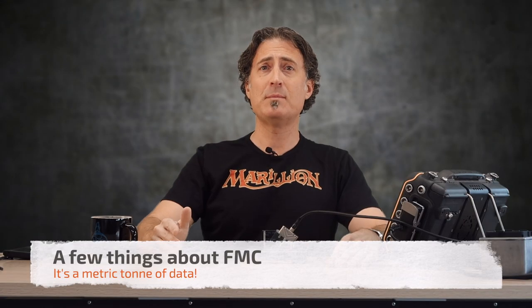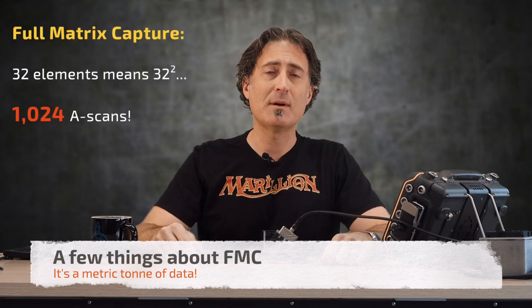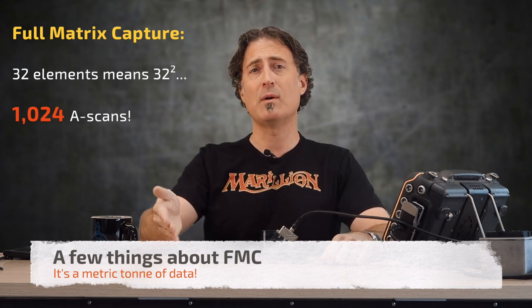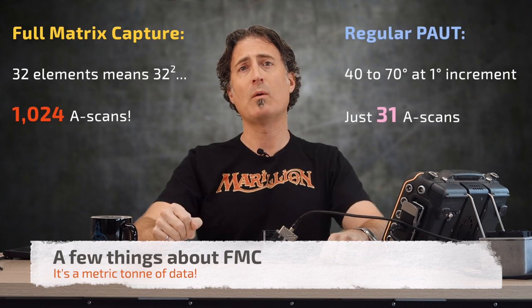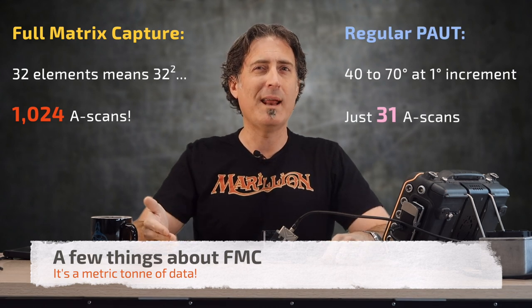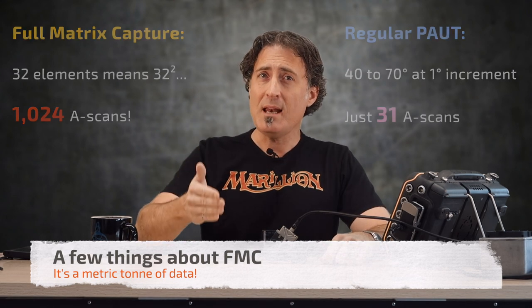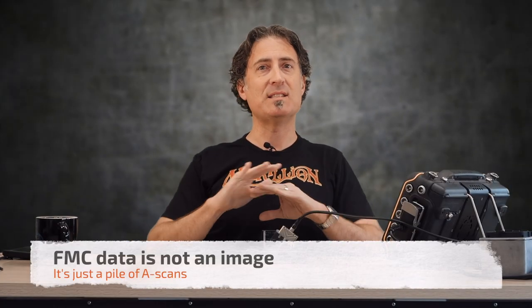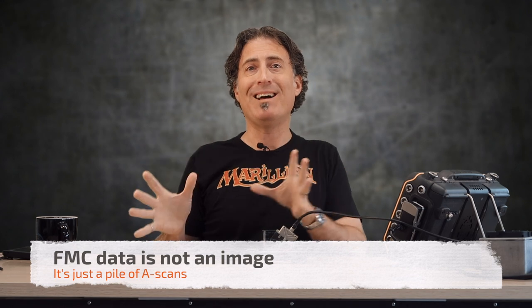A few things about FMC. Number one, it is a ton of data. With a 32-element transducer, you've got 32 squared, or 1024 A-scans. Compare that to regular phased array — say 40 to 70 degrees in a one-degree increment — you have 31 A-scans. You can store FMC data raw and process it later, but from a data storage standpoint, it's not really practical. And FMC data by itself is not an image — it's just a pile of A-scans.